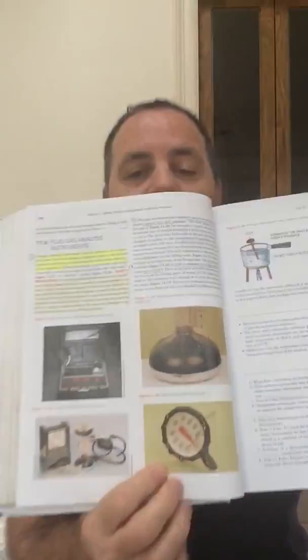Now, the thermometers they use usually measure temperatures up to 1,000 degrees Fahrenheit. And I will tell you this, with flue gas analysis equipment, if you have a combustion leak detector or anything like that, they're not going to let you calibrate it. Why not? Because you have no business opening up those kinds of tools and fooling with the settings. You have to send them in if they're not right, to get them repaired by the manufacturer or someone who knows what they're doing.